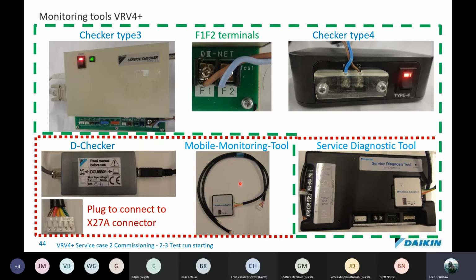Right, so what is not a checker or a D checker or a monitoring tool? It's not a crystal ball that we plug onto a system, and it automatically jumps up and says, you have a fault, you have swap piping, or you have swap wiring. There is a tool that gives us information and data, and from that we have to diagnose. So we have a lot of guys who are asking, okay, well, when can we buy this? Well, first of all, the checker tools are not for sale, but the D checker and monitoring tool are. But when you purchase these, you must realize that you're getting information from a machine. You still need to make a call on that information. So it's very important that you actually understand how the system operates, so that you're able to discern that information into some sort of fault report.